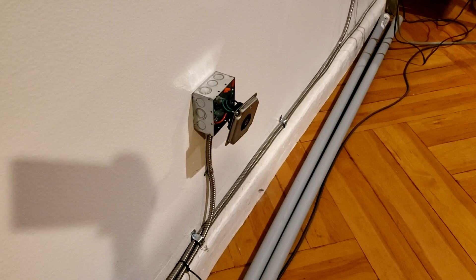And then the other thing I have to do is this outlet was wired incorrectly. It's wired for 220 volts and it should be 110 volts. So I have to rework that one and make sure it's correct. And so I need to determine which one of the neutral wires is the one that goes to that box, because I need to reconnect the neutral and disconnect one of the hot wires, like the red one, and then I'll need to determine which one is the red one that goes to that. It should be this breaker here, this 30 amp breaker. That should be the wire. I'm sure it is, but I'll need to disconnect one.